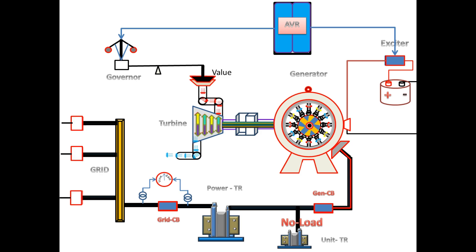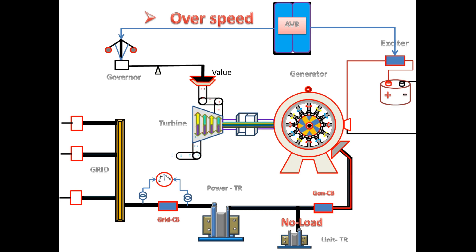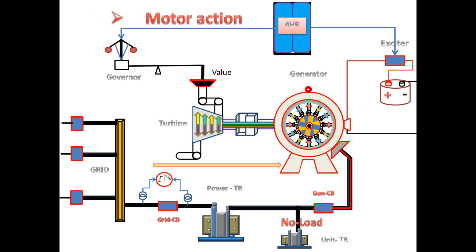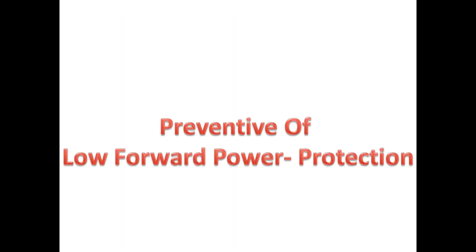In a few cases it produces over speed to the turbine, since the rotating and speed control are mechanical — they are not able to reduce the speed suddenly, and the rotating parts are designed for some maximum inertia only. If it rises more than that, it may affect the mechanical parts. In some other cases it leads to motor action: when the turbine does not have sufficient steam to produce power, or the turbine trips, then the power from the grid will start to flow towards the generator and it will lead to motor action.